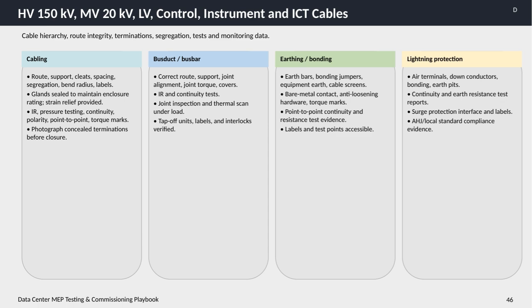Next, earthing and bonding systems need careful attention. Earth bars, bonding jumpers, equipment earth connections, and cable screens must have bare metal contact supported by anti-loosening hardware. Torque marks provide evidence of proper installation. Point-to-point continuity and resistance tests confirm electrical integrity. Labels and test points should be accessible for maintenance and verification.